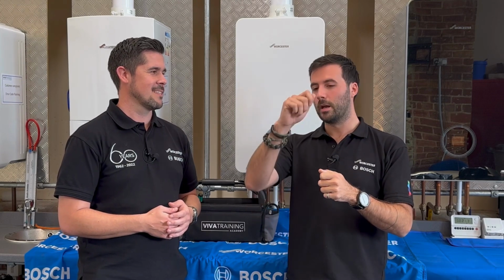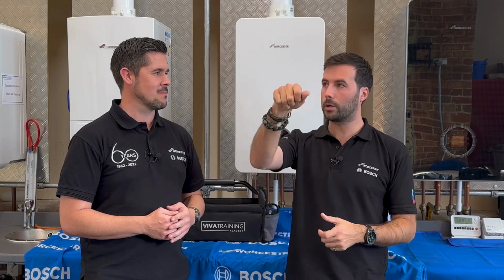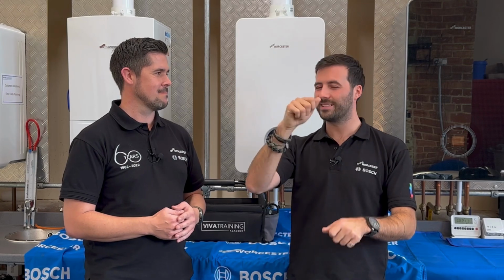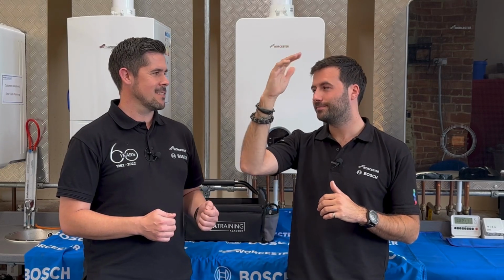So how do I diagnose a blocked plate heat exchanger? Well, there's a couple of ways you can do it, but I think probably the best one is to run the boiler in hot water, as you normally do, and if everything's working just as it should, you should have no more than 10, maybe 15 degrees, between the flow off the main heat exchanger, so that's the water to your taps, compared to the temperature of the water going into the plate. So most people have got an analyzer, most of you have got two clamps, one on the flow into the plate, one on the hot out. They should be within about 10 degrees of each other. If it's creeping up and going further, you've probably got a blocked plate.